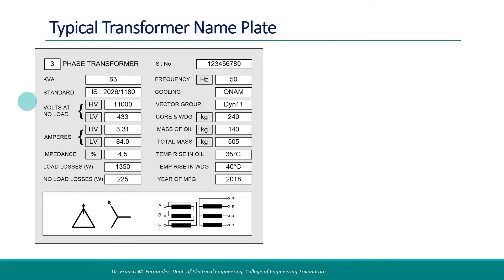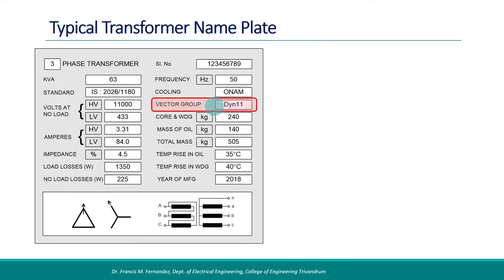The details of the transformer are printed on the nameplate, that include the kVA rating, the voltage on the primary and secondary sides, the currents, the percentage impedance of the transformer, the frequency of operation, type of cooling, the weight of the transformer parts, and the possible temperature rise. In addition to all these things, the vector group is also specified and here it is given as dyn11.